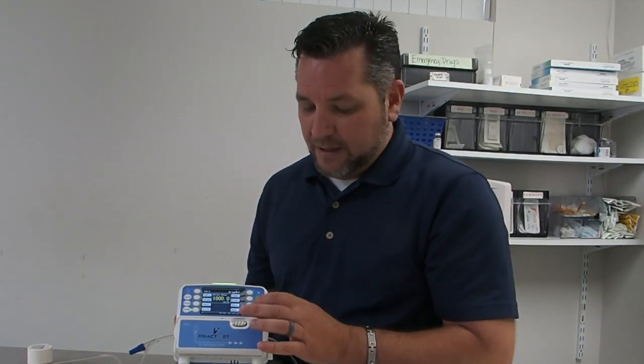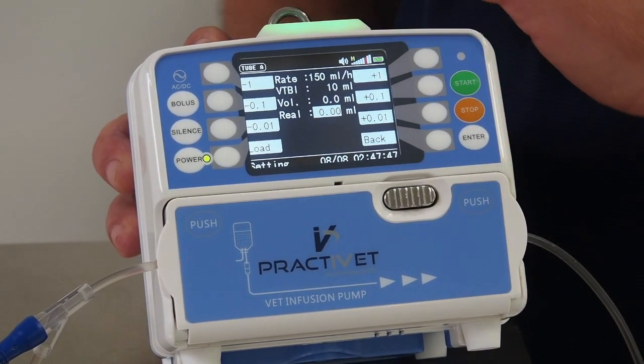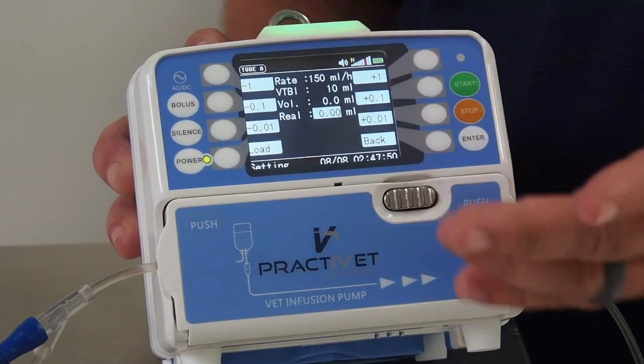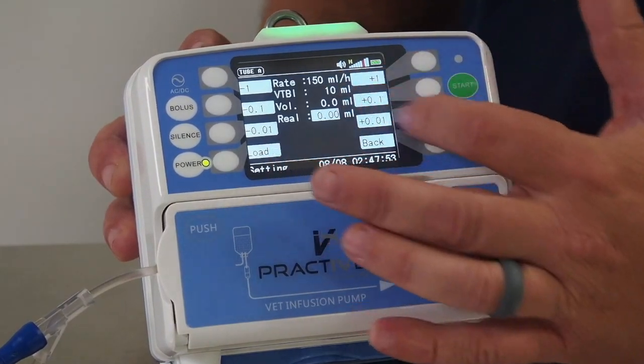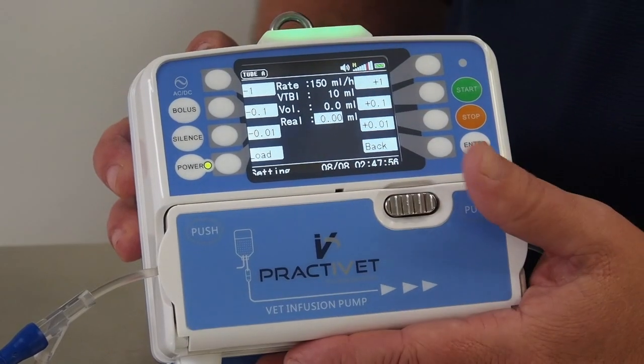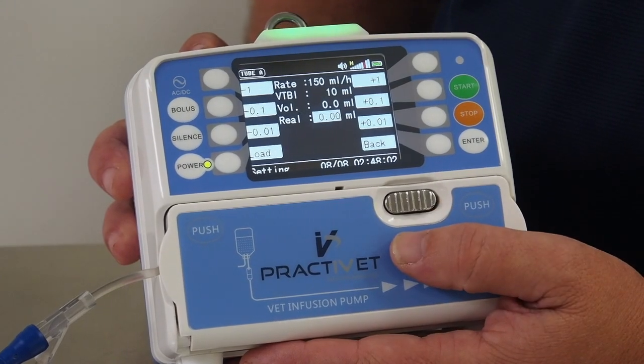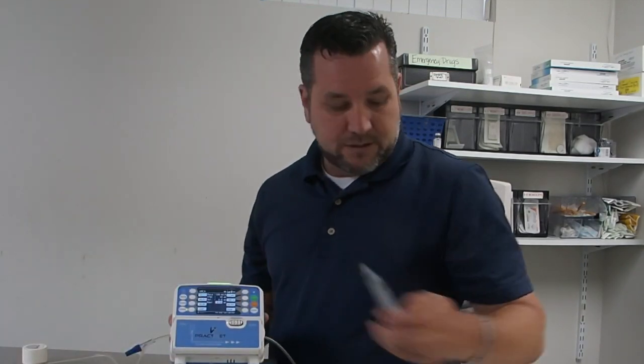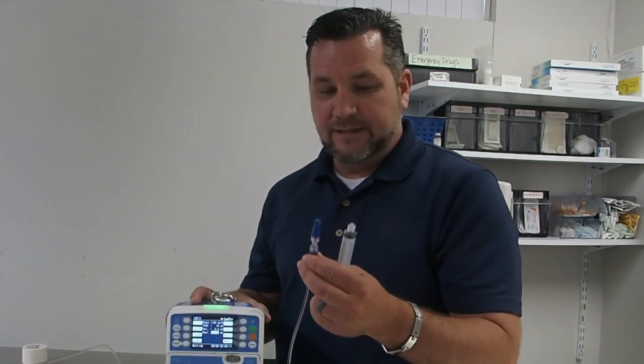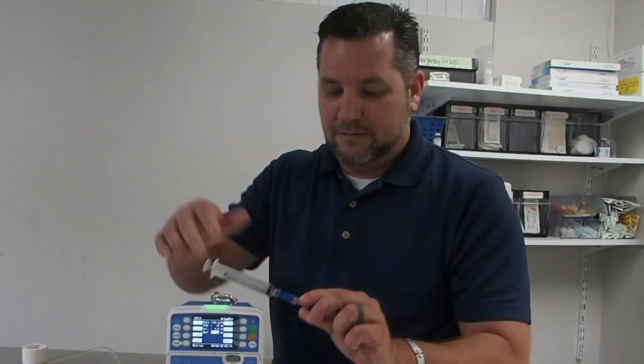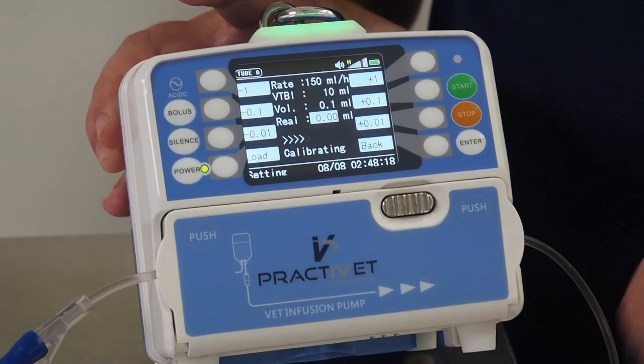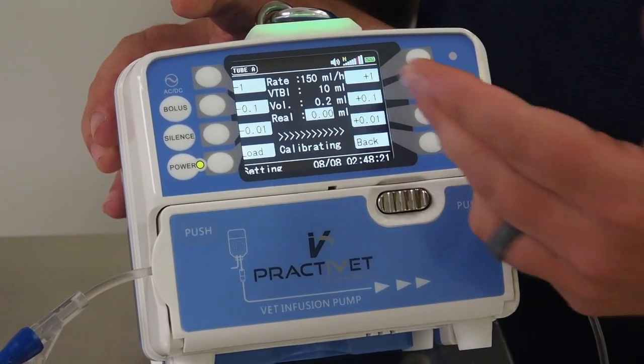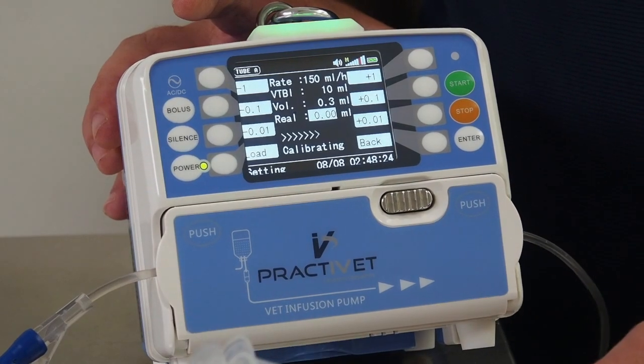Another valuable feature of the Practivet infusion pump is the accuracy button. This feature will allow you to recalibrate this pump in-house in about 3 minutes by simply hitting the accuracy button. The pump is going to tell you that it's going to run 150 mils an hour at a 10 mil volume to be infused. It is recommended that you use a 10 mil syringe connected to a transfer device. Once you hit start, the pump is going to go through its calibration procedure, in which it will pump 10 mils into your 10 mil syringe.